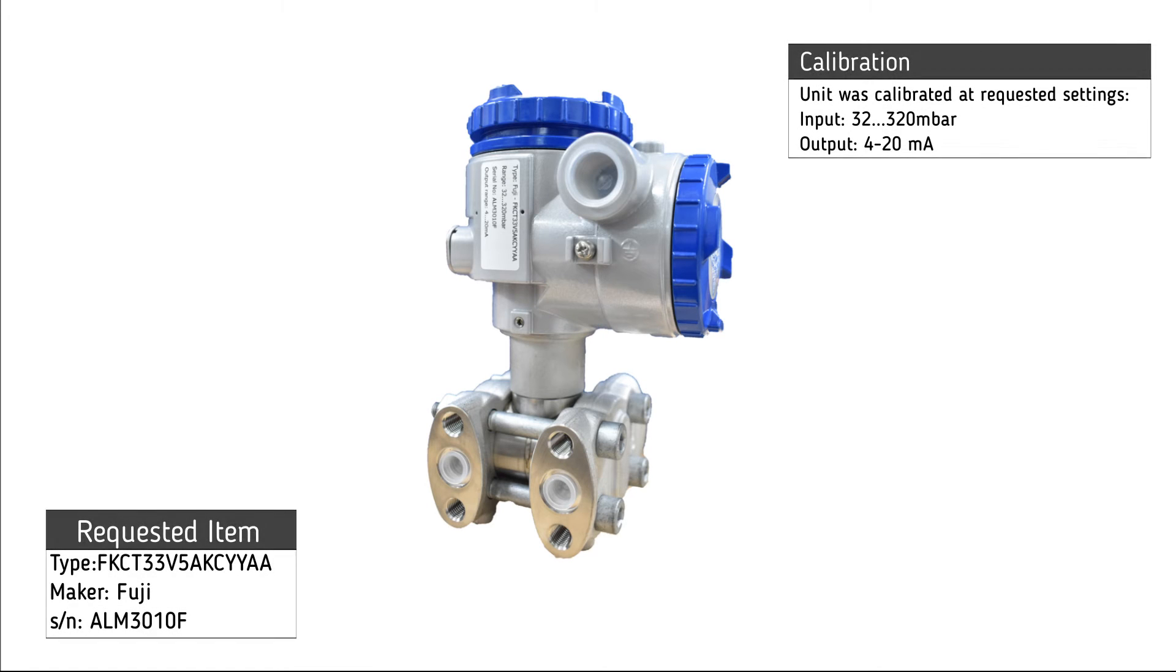Testing of Fuji differential pressure transmitter. The transmitter has been set to a calibration range of input signal from 32 to 320 millibar.